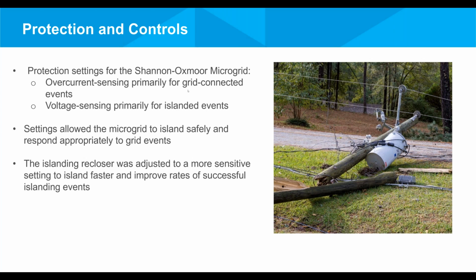For grid-connected systems and grid-connected events, overcurrent sensing is primarily used. But in the case of an inverter-based system, when there's a fault, the current is usually low. So voltage sensing is introduced in order to help for islanded events. And these settings allow the microgrid to island safely and respond appropriately to grid events. Furthermore, for the islanding recloser, well, there are two reclosers. In between the microgrid and the smart homes, there's a recloser, which is called the DER, Distributed Energy Resource, recloser. And then in between the smart homes and the main grid, there's the Power Control Center recloser. So the islanding recloser was adjusted to a more sensitive setting to island faster and improve rates of successful islanding events.